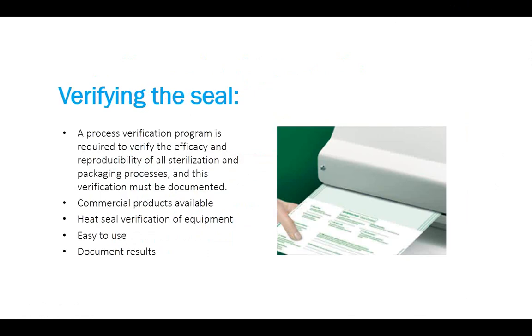So how do you verify the seal? There's something very simple. There are commercial products available, as you can see here, that you run through your heat sealer. You can put the date and time, and actually look at the seal to make sure there are no rivers or gaps, and then document it.